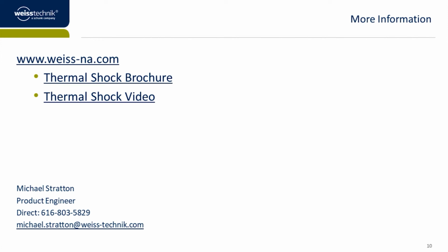The next question here, what other parameters such as expansion are studied? How is data being acquired? So thermal expansion is the main area of concern for thermal shock chambers. However, the others are just if the device can operate at extreme highs and extreme lows. So that's another area of study.